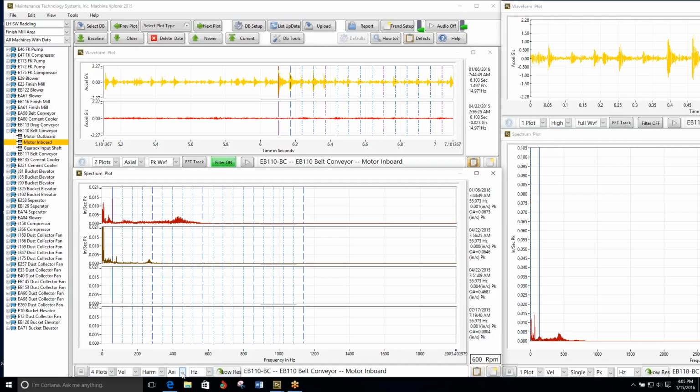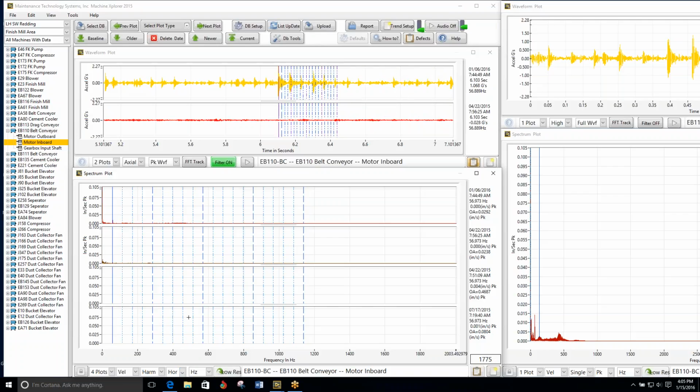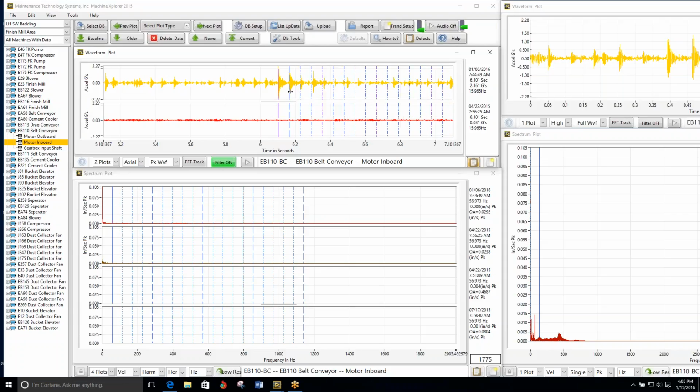So I noticed that you just aren't seeking after all that much accuracy. You get close to a frequency in that time waveform. Yeah, I would sit there and fiddle with it till I nailed it. But you get out here and you say, well, if it's a 900 RPM shaft, and that's close to 900 RPM, we can fiddle around all we want, but it doesn't change our analysis.